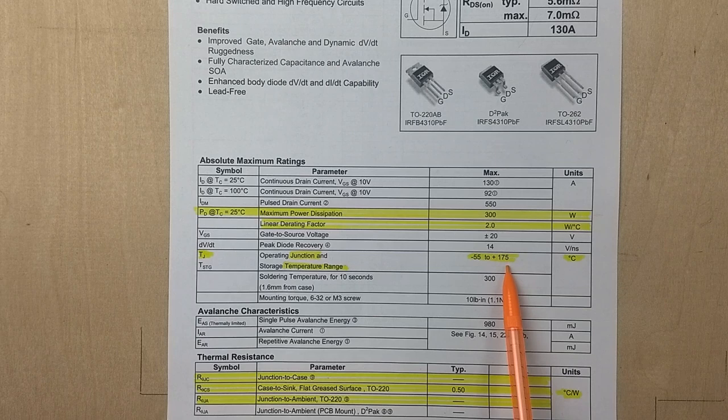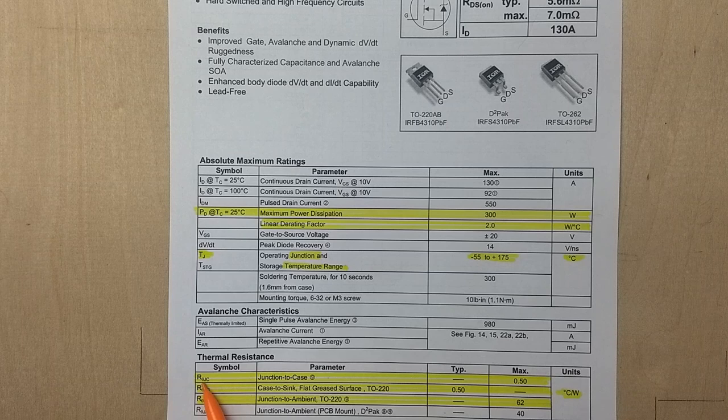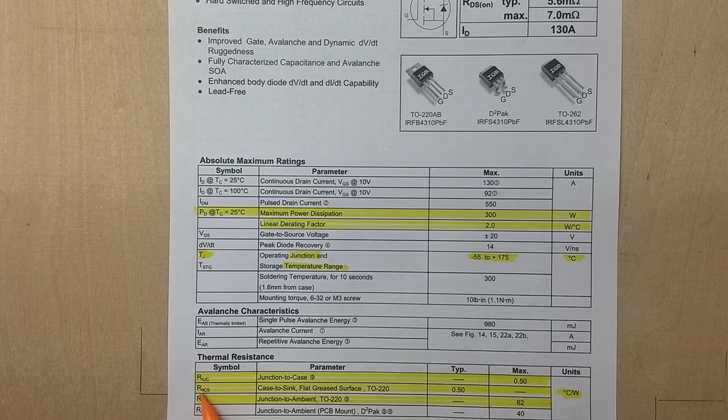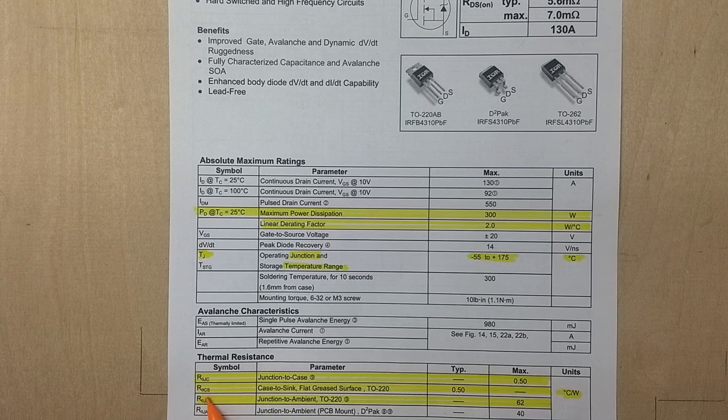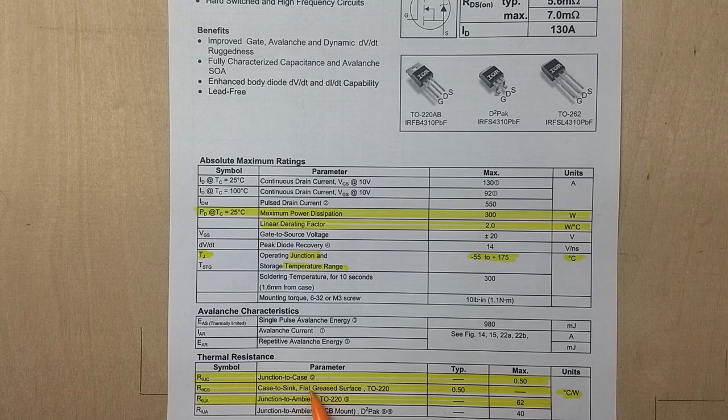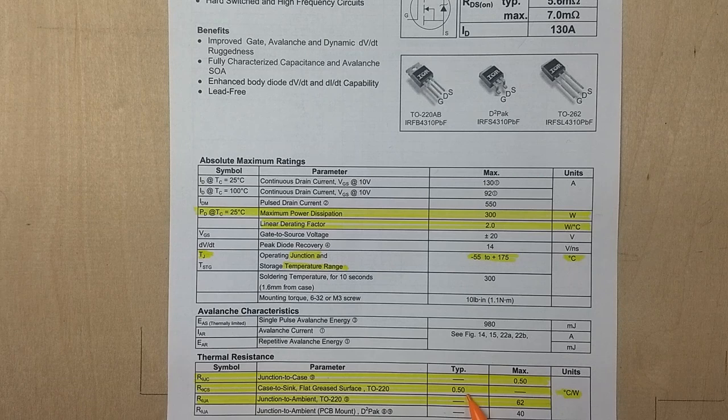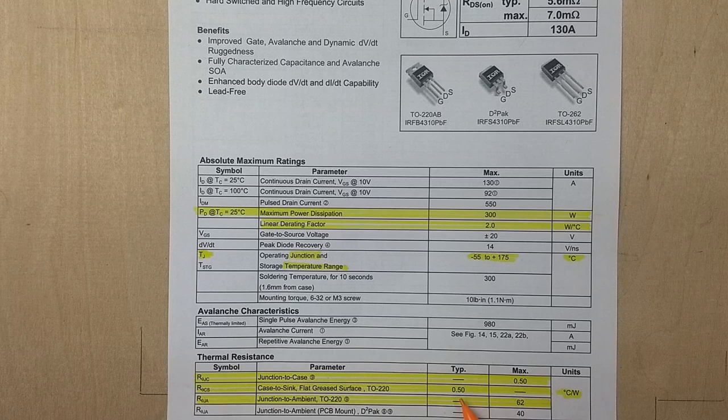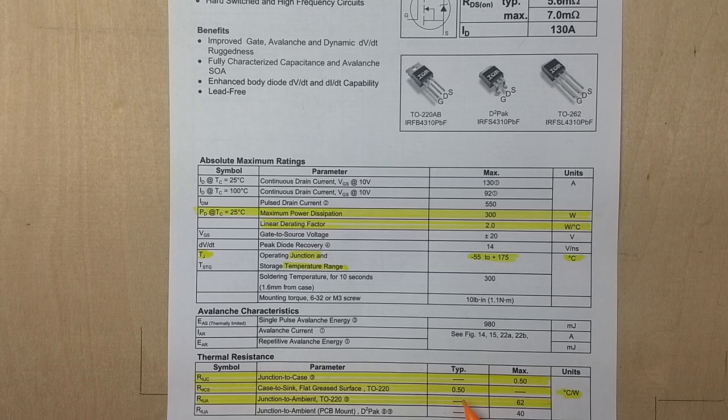Then down here they're telling us the thermal resistance junction to case is 0.5 degrees C per watt. And this is a very important parameter, this next one. The thermal resistance case to heat sink, and let's assume it's smooth, flat, and greased, is also 0.5 degrees C per watt. And this is going to turn out to be a very important factor when we look at heat sink sizing.